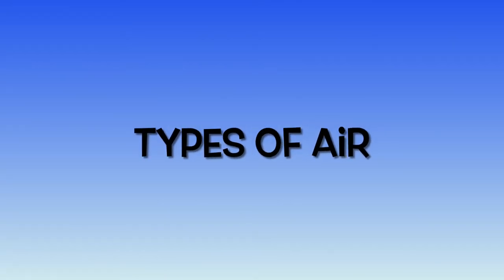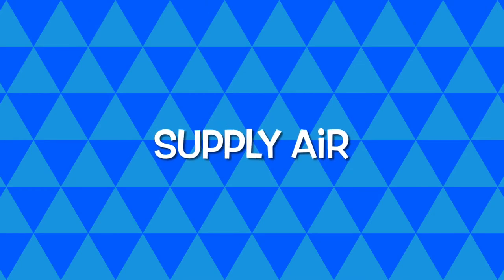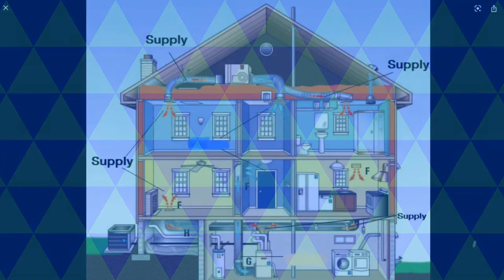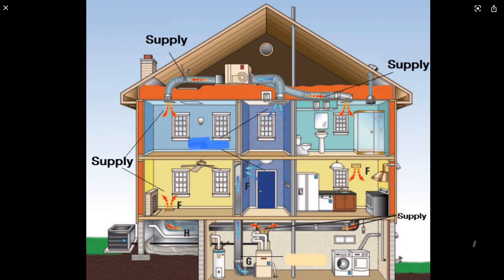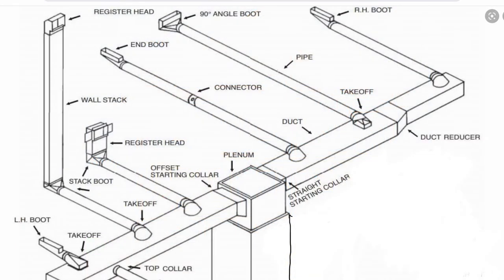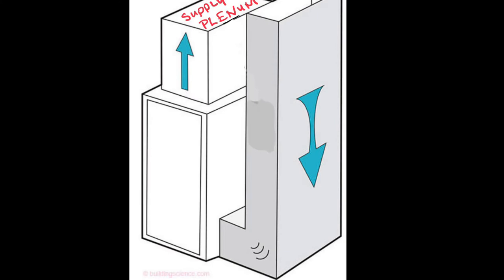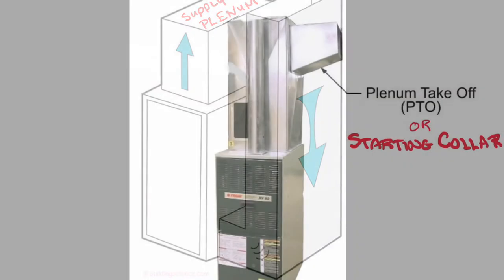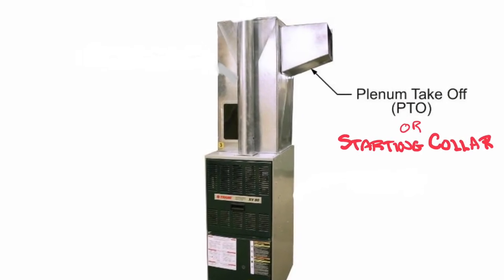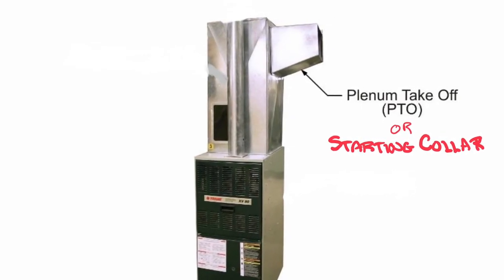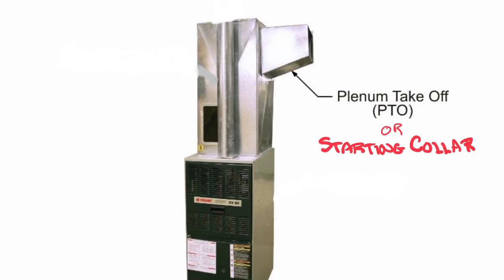My next topic is going to be the types of air flowing or not flowing through your home. The first one being supply air. The supply air comes from an air handler or a furnace. It's the one pushing air through the ductwork system into every room. First of all, you have the furnace, then you're going to install a supply plenum, and then off that plenum, we need to install a plenum takeoff or starting collar.